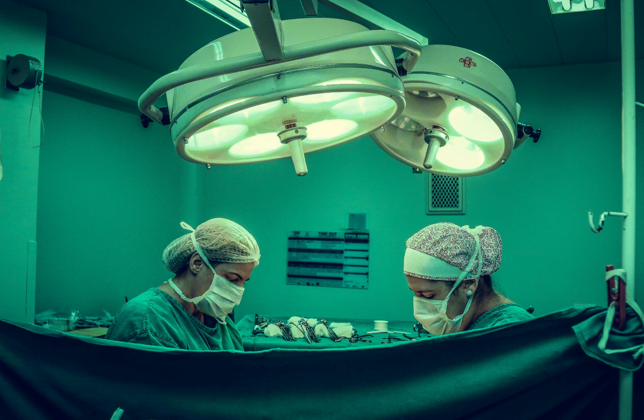This one step alone can eliminate most insulation-related burns. Solution 2. Visual inspection under magnification. All insulated instruments should be inspected under lighted magnification as part of a routine quality control. Even if an instrument looks intact, SPD techs need to be trained to look for the signs of damage, discoloration, peeling, dents, or soft spots that could indicate insulation wear.